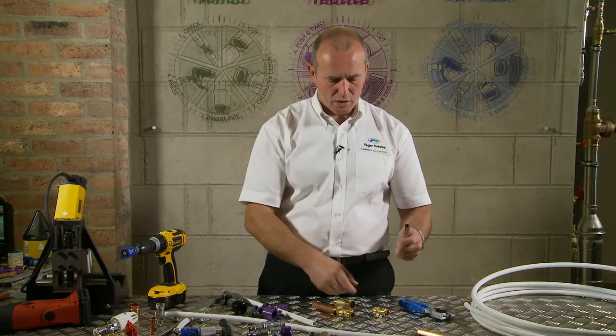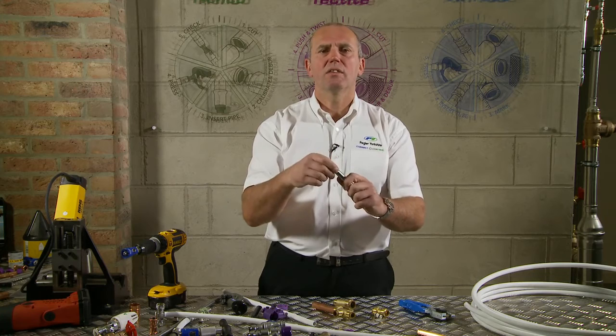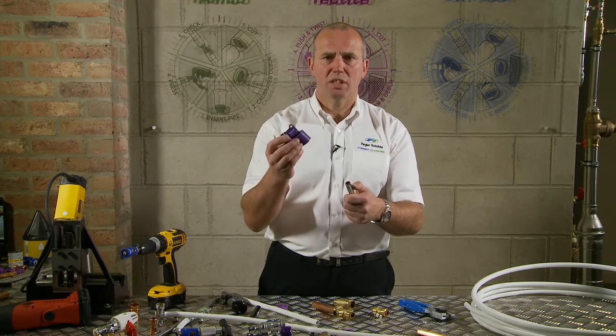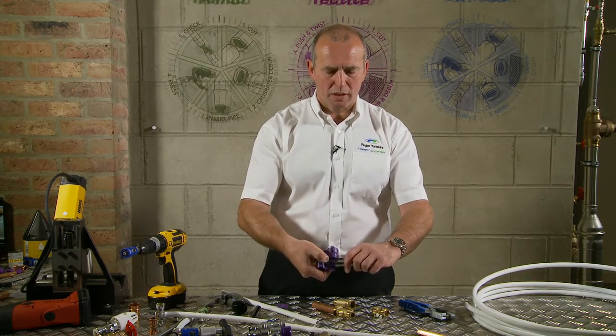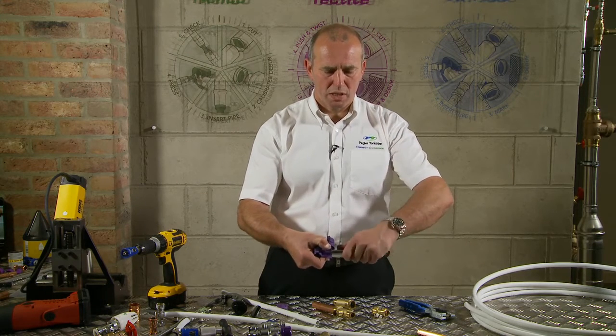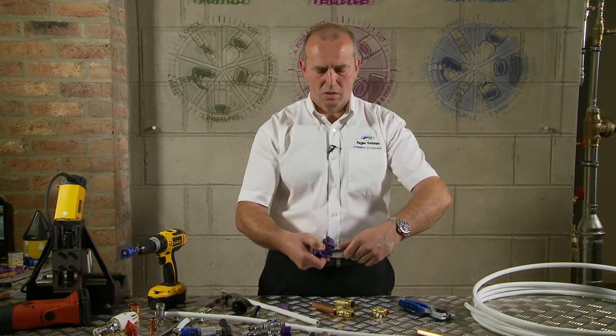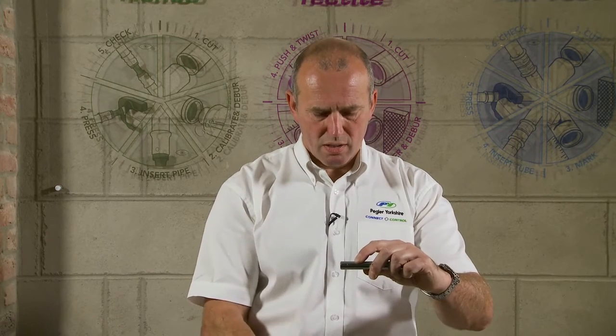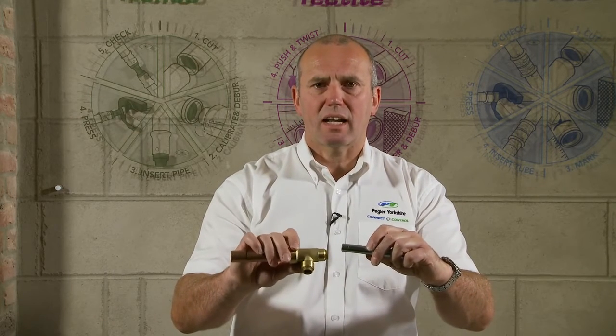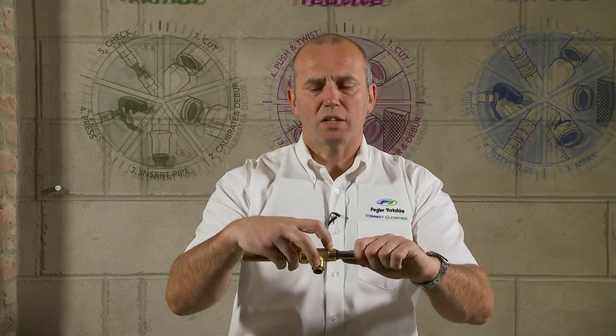Then we will move onto the chromed copper pipe. This copper pipe generally you would have to file the chrome off the pipe if you were doing it onto a solder ring fitting, or with a lot of push fit fittings you wouldn't be able to use the chrome. Whereas with this, you once again use the Tectite depth marker — insert it into the 15mm and the black scribing pip there. You push in and then twist the pipe, pull it out, and there you can see the scribe mark. So once the scribe mark is made, you offer it up to the Tectite Classic fitting.